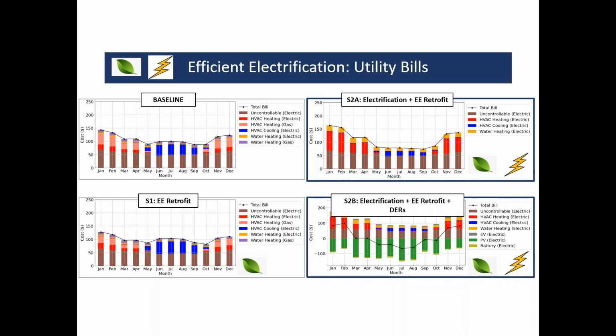So let's look at scenario 2A. If I were to show you corresponding graphs plotted in energy units, you would actually see that the efficient electrification scenario in 2A uses slightly less source energy than even the conventional efficiency retrofit in scenario 1. But on an annual basis, the utility costs to homeowners are nearly identical to the baseline, because the higher cost of electric heating in the winter offsets the cooling savings in the summer.